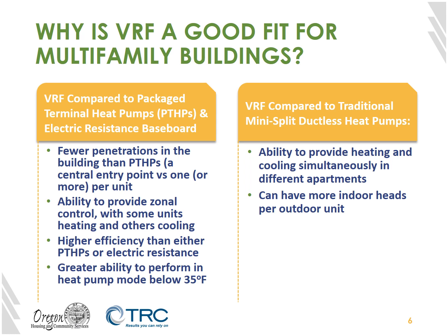Finally, VRF systems can excel at a variety of outdoor temperatures and at a variety of loads inside the building. So whether we're talking about producing useful heat even in very cool temperatures or useful cooling power even in very high temperatures, VRF systems work terrifically. They also work really well and very efficiently in what we consider a low load scenario, or when it's just a little bit cooler or a little bit warmer inside of our units than it is outside. That effectiveness throughout a wider range of outdoor temperatures and different load profiles of our building really makes VRF systems special and allows them to operate at their peak or close to peak efficiency at a wider range of temperatures.